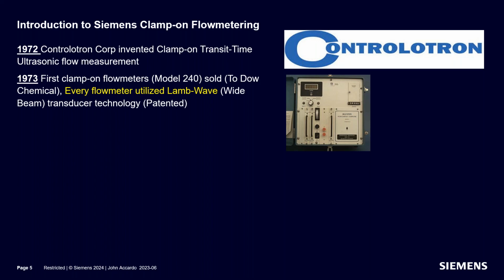Every single flow meter that we built back then and right through to the current day utilized Lamb wave techniques and Lamb wave technology, wide beam as we called it, which referred to the way the ultrasonic wave presented itself as it traveled across the pipe. So Controlotron developed and deployed the wide beam ultrasonic transit time flow meter. It was the only one of its kind at that time, and as I said, it utilized the Lamb wave from the beginning, and that technology was patented by Controlotron. So we were the only ones that offered Lamb wave technology.